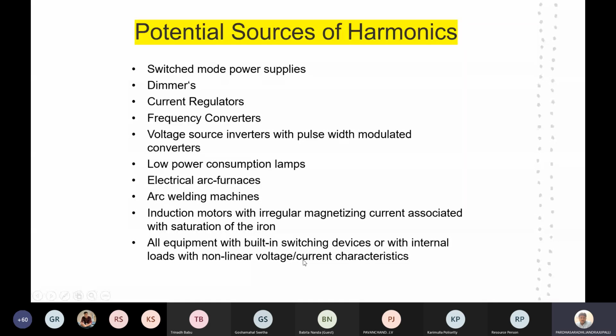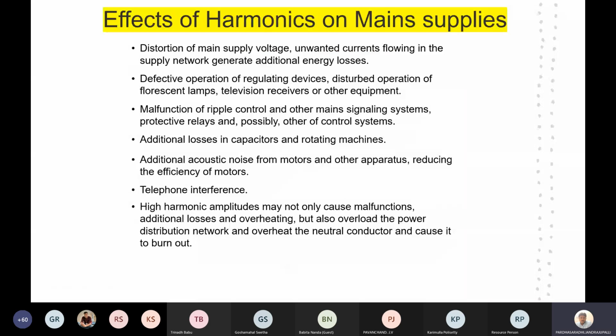What are the effects of harmonics on mains supplies? Distortion of the mains supply voltage, and unwanted current flowing in the supply network, generate additional energy losses. These losses include I squared R losses. Once these harmonics are injected, the losses are proportional to more than before: earlier the losses were I RMS squared times R, but after injection the losses become a function of the harmonic currents also, that is, the total harmonic distortion. So the losses are going to increase.